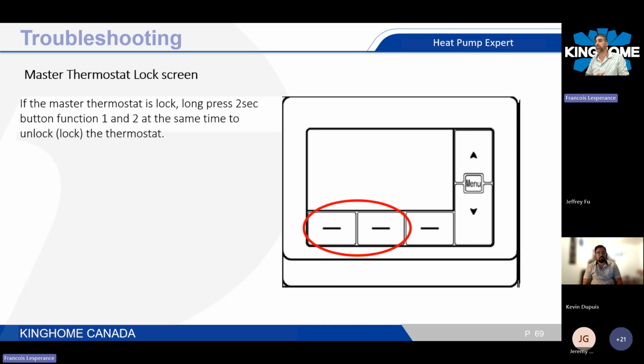The master thermostat can also be locked if you don't want the homeowner to come down to the mechanical room and play with that thermostat. The only use of this one is for you, when you are doing maintenance on the system or troubleshooting in front of the furnace. The great thing about it is you don't have to pull out jumper wires or anything. You can just perform a heat or cool demand directly using the thermostat.